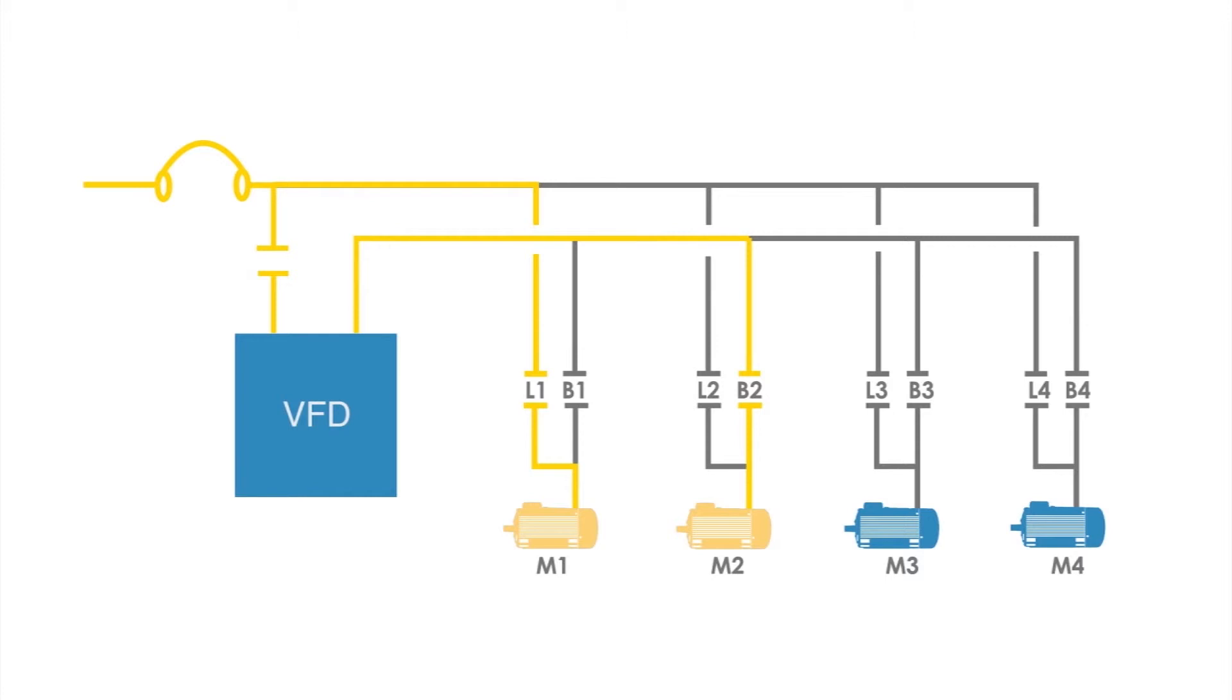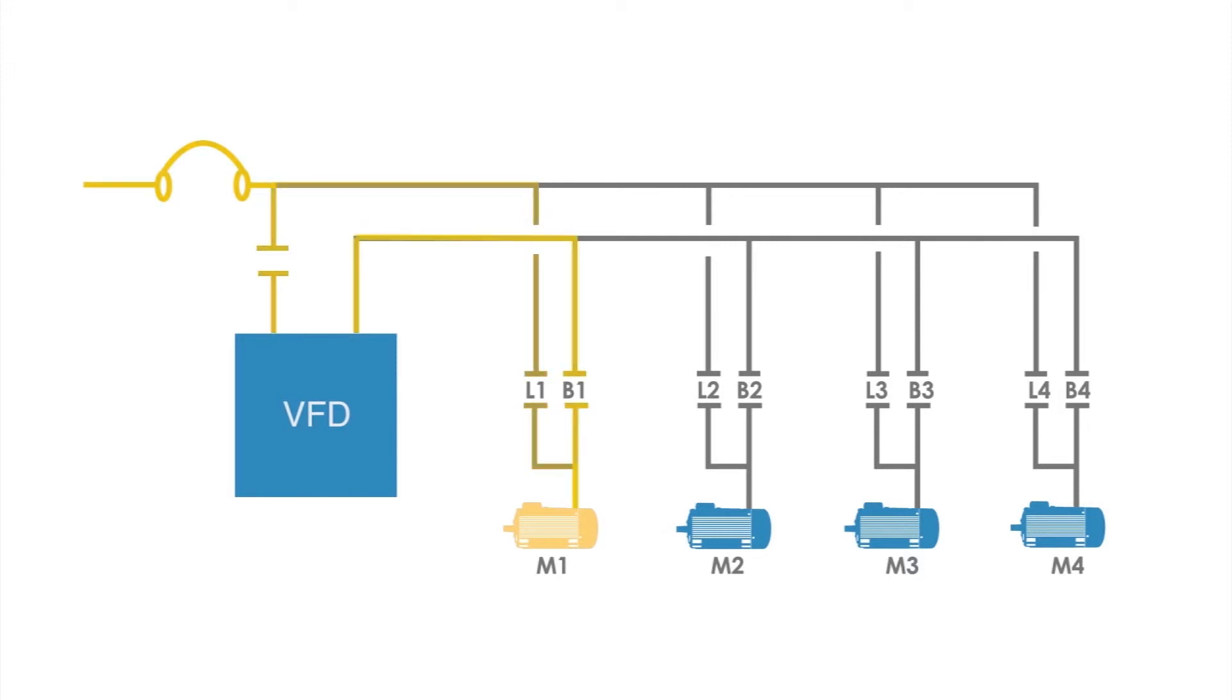The across the line transfers can also be done in a reverse direction. If we no longer need two motors or pumps running, the VFD commands motor M2 to zero speed and then opens contactor B2. The VFD output is synchronized to the incoming line and contactor B1 is closed. Motor M1 is transferred from the line back to the VFD output and is now running on the VFD at variable speed.